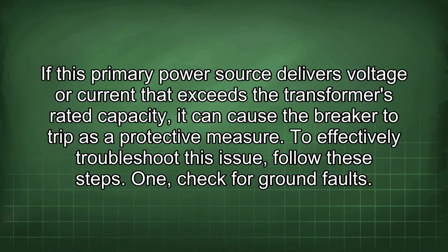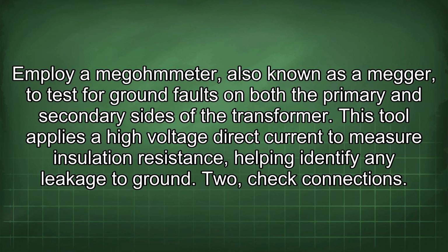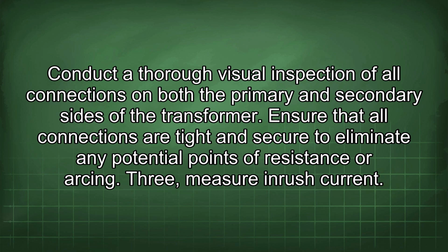1. Check for ground faults. Employ a megohmmeter, also known as a megger, to test for ground faults on both the primary and secondary sides of the transformer. This tool applies a high voltage direct current to measure insulation resistance, helping identify any leakage to ground. 2. Check connections. Conduct a thorough visual inspection of all connections on both the primary and secondary sides of the transformer. Ensure that all connections are tight and secure to eliminate any potential points of resistance or arcing.